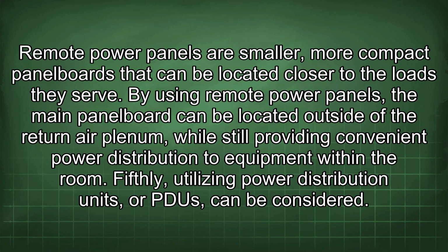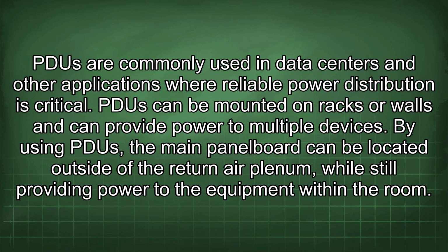Fifthly, utilizing power distribution units, or PDUs, can be considered. PDUs are commonly used in data centers and other applications where reliable power distribution is critical. PDUs can be mounted on racks or walls and can provide power to multiple devices. By using PDUs, the main panel board can be located outside of the return air plenum while still providing power to the equipment within the room.